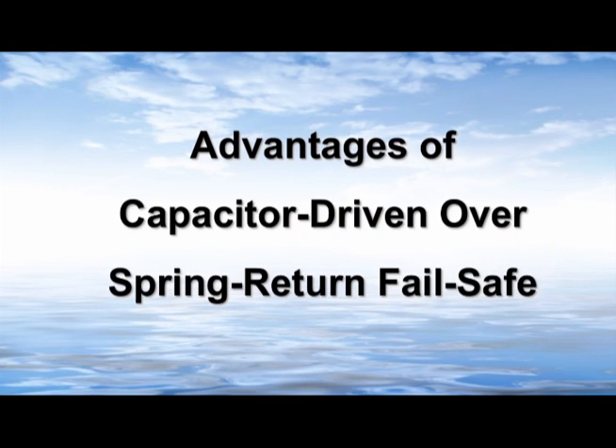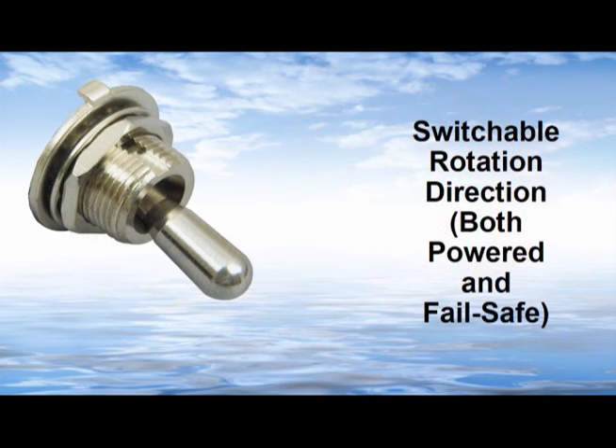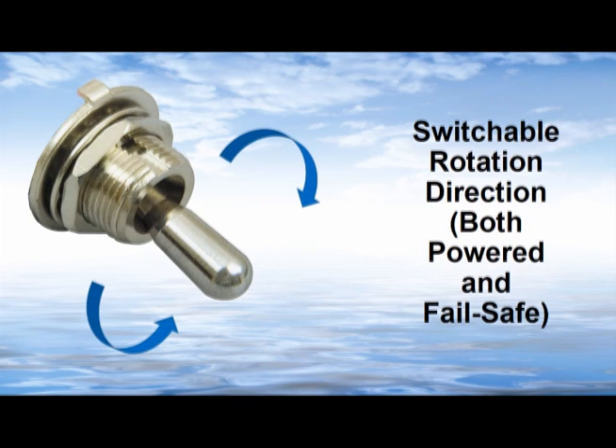Capacitor driven failsafe models provide multiple advantages over spring driven actuators. Capacitor driven actuators usually have smaller cases, weigh less, and can attach to shorter shafts than bulkier spring returns. Capacitor driven actuators provide switch selectable failsafe and power directions, so that one model can easily be used for both clockwise and counterclockwise failsafe applications without flipping over the actuator and changing the shaft clamping mechanism.